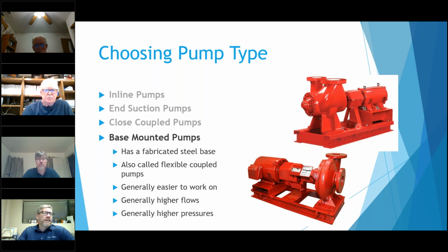The vibration is usually a lot less with this fabricated base. Especially when you get grouting in there, it adds all this extra mass and rigidity to that base. The vibration tendencies with base mounted pumps are a lot less. And according to the Department of Energy data, base mounted pumps also last quite a bit longer than inline pumps or close coupled pumps. They just can handle the wear and tear better than those types of pumps. So they can usually last, I think it's almost another 10 to 15 years, I believe, longer than even a vertical inline pump that's separately coupled.